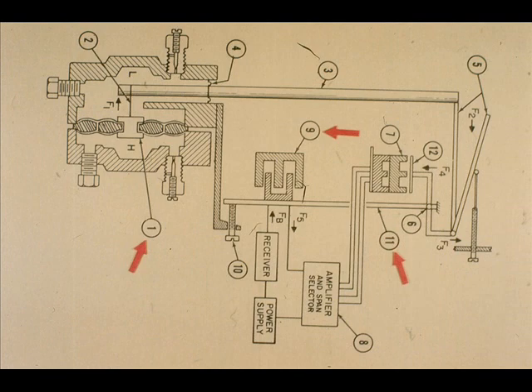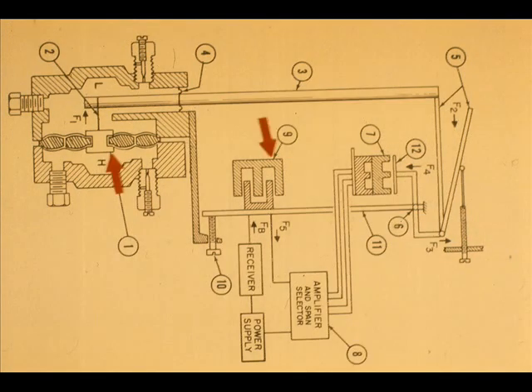The DC output is fed to the receivers in the loop and also to the feedback motor 9. The feedback motor 9 exerts a force on the lever system in opposition to that produced at the diaphragm capsule 1. 10 to 50 or 4 to 20 milliamps through the force motor 9 will balance the force across the capsule within the calibrated range of the transmitter.